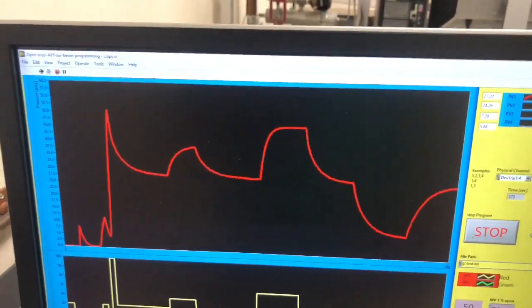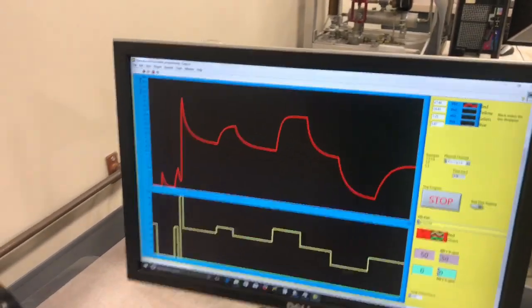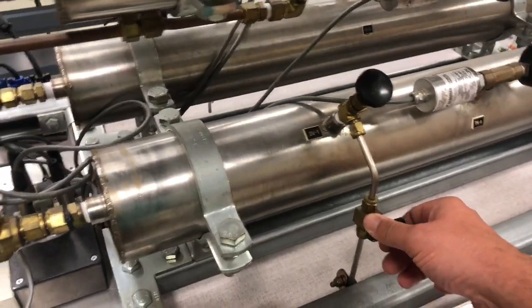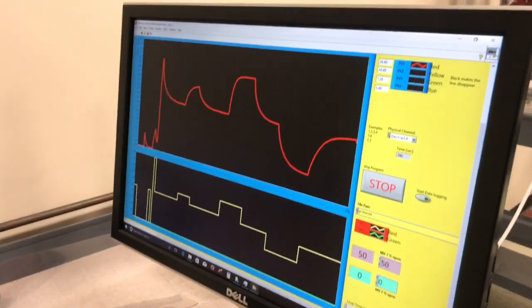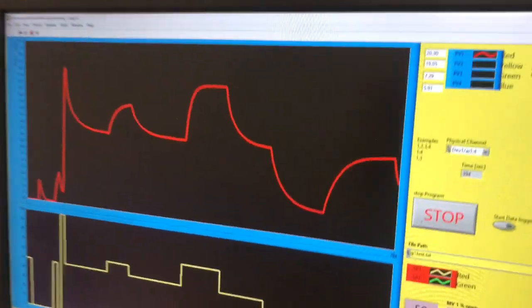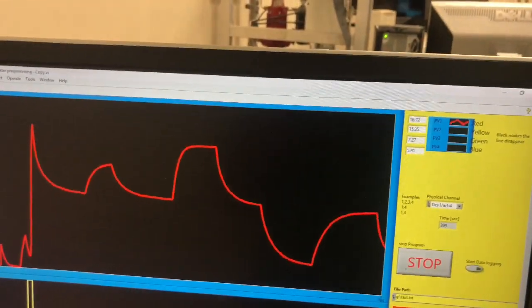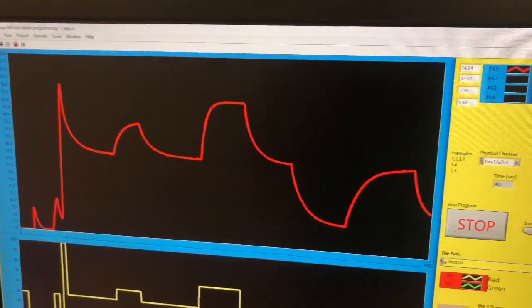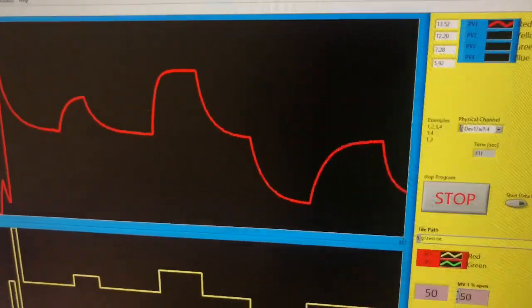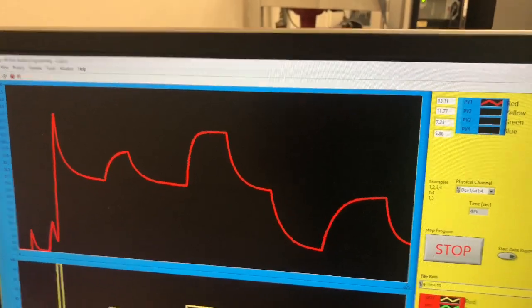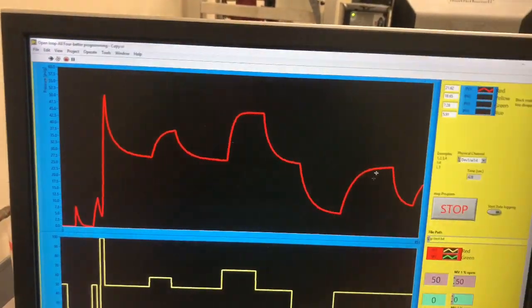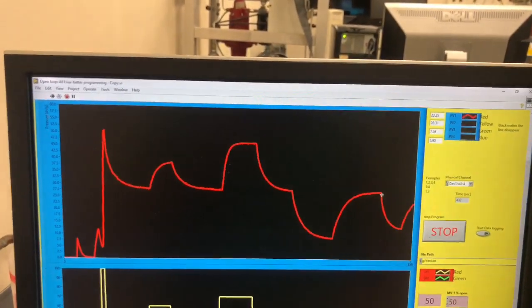So that's our manipulated variable. You have on your response data that you've been given another set of data that represents a disturbance, an unmeasured change. And we can simulate that with a manual valve. I'm going to open this valve and create a change in the tank pressure. I'm going to do that right about now. But we're not measuring that valve position. We don't know what that valve is, what's going on. That's a disturbance. Some yahoo could go in and open that valve, close that valve, and it will put a system response, a forcing function, an unknown forcing function, that disrupts our process. We cannot model that because we don't know exactly when or to what extent that valve changed. So all we can do is model the other parts of the process where we have inputs that are changing and pushing the system around.